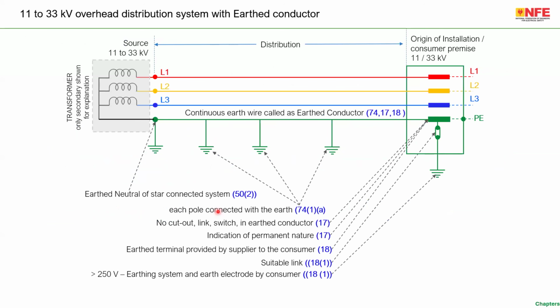If we put these regulations in a pictorial form, you will find this one. For example, for the picture, I am only showing the transformer, only the secondary is shown for explanation. Only the star, the secondary winding of the 11 kV or 33 kV source is shown for the explanation. Then there are 3 lines in the distribution. Actually, it's not 3, it is 4 metallic wires, L1, L2, L3, and the continuous earth wire, which is called the earthed conductor in regulation 74.